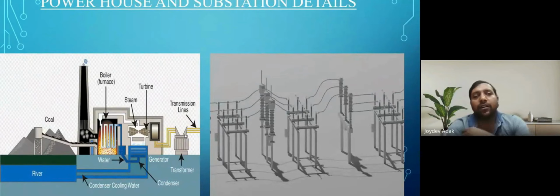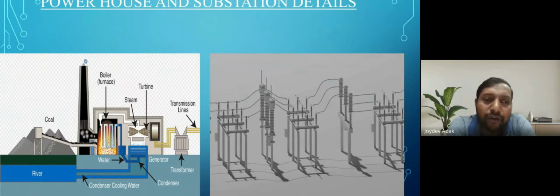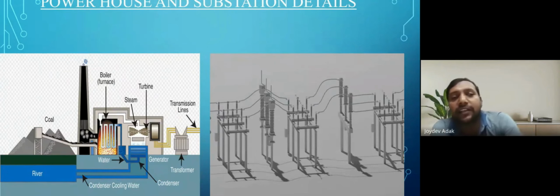So here one question is why this is done in the power system. Why is the generator voltage not increased to that level? The generator transformer costs around 20 to 30 crore for a 210 megawatt unit, and there is maintenance cost also. Can anyone say why the generator uses a low voltage level and then we use a generator transformer, in spite of the cost of the generator transformer?